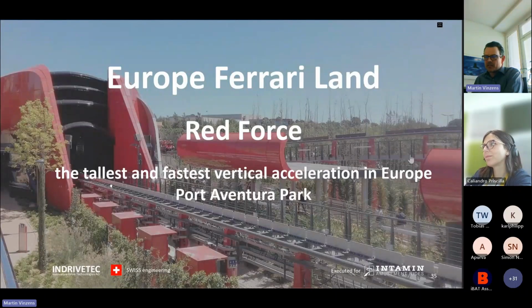Here we delivered the motors, and here you see the outdoor inverters basically driving or feeding the energy to the motors here on the track. So this is a spread, basically DC system, DC bus connected to grid and storage, so that the peak load is fed out of supercap storage and not coming directly from the grid.